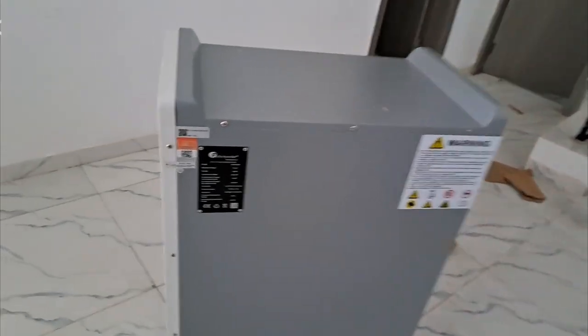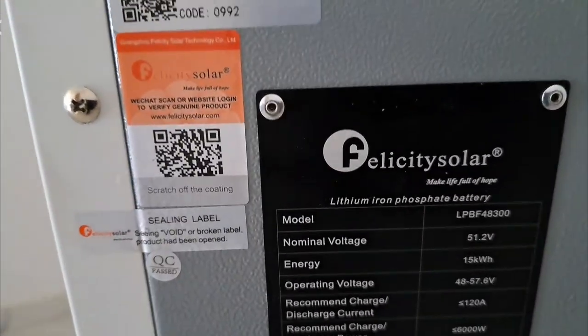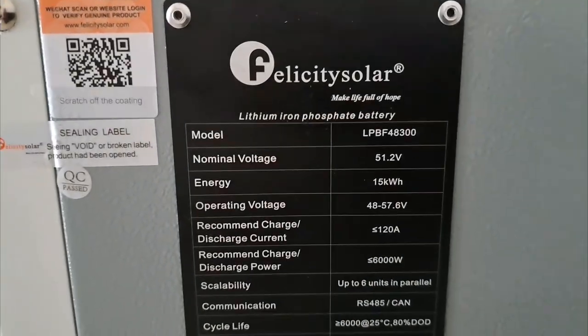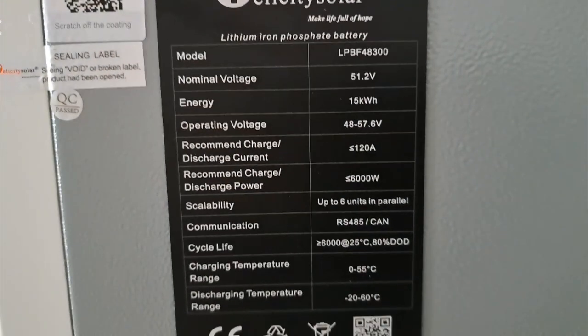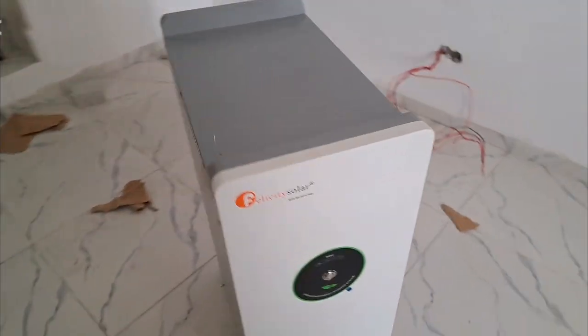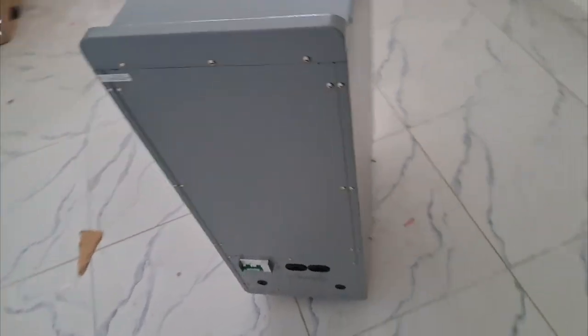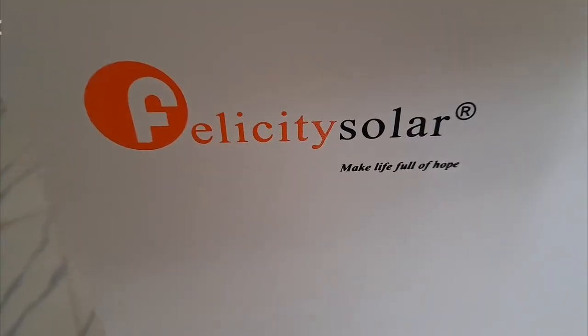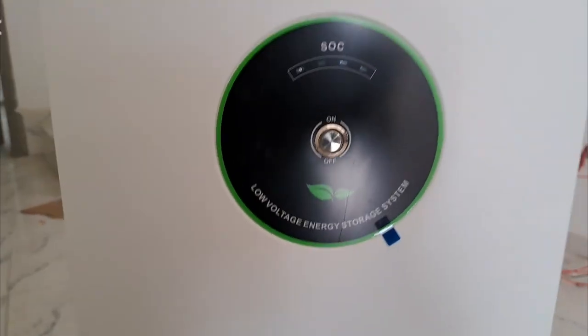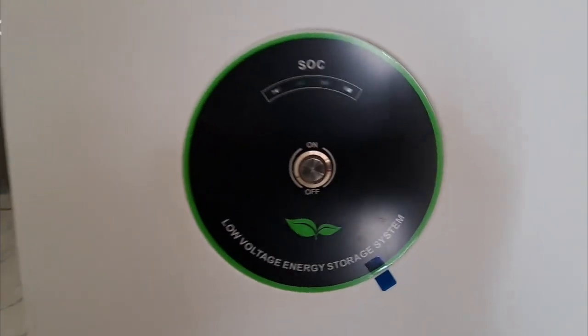These are some of the experiments I'll be doing so you can see exactly what I mean. When we say a battery has about 80% depth of discharge, most lithium-ion batteries actually reach 90 and even 95%. Taking 80% of 15 kilowatt hour lands us around 12.5 kilowatt hour that we can get from this battery. Assuming we're using the full load from our 6,000 watt, 7.5 kVA inverter, we'd be pulling 6,000 watts for 2 hours. So if we put full load on the inverter with a fully charged battery, it will take 2 hours to fully discharge it. In future I'll be doing more analysis on this.